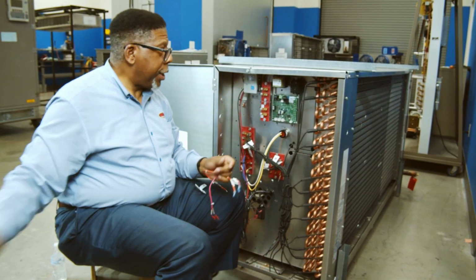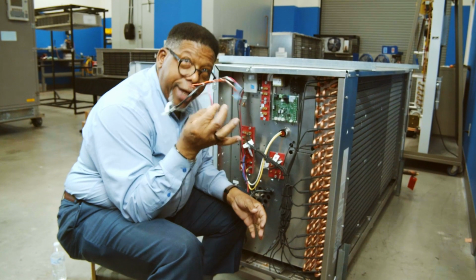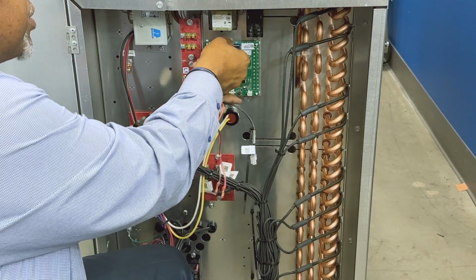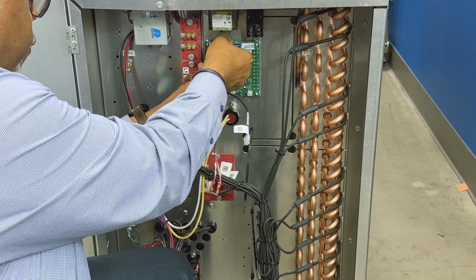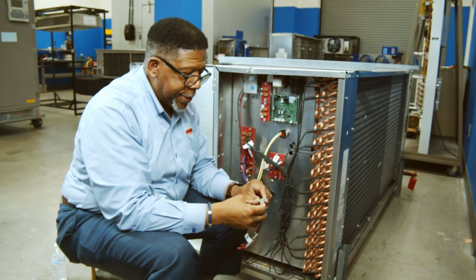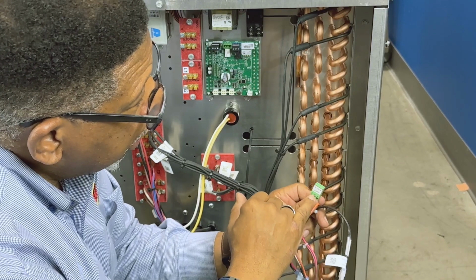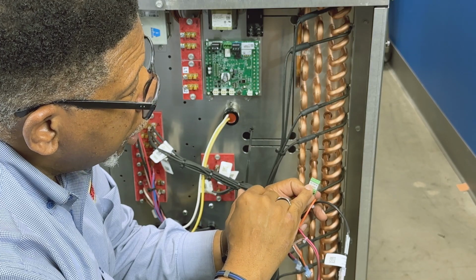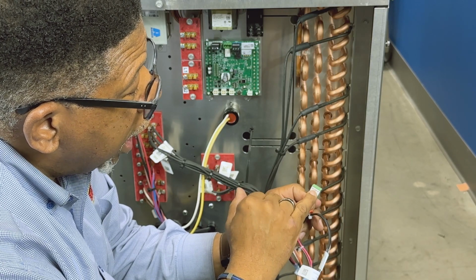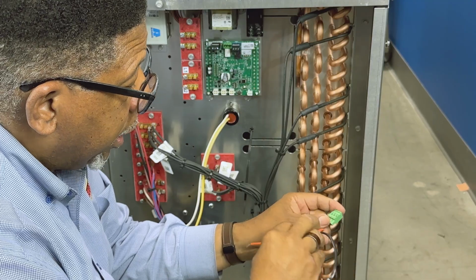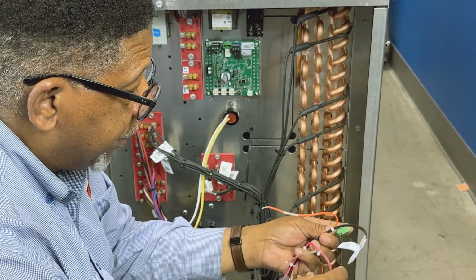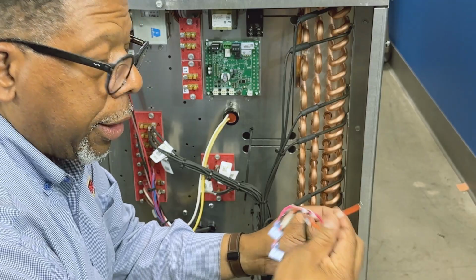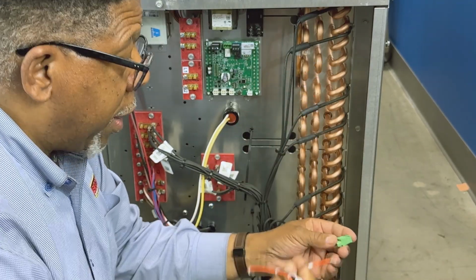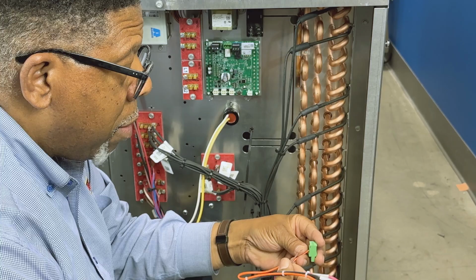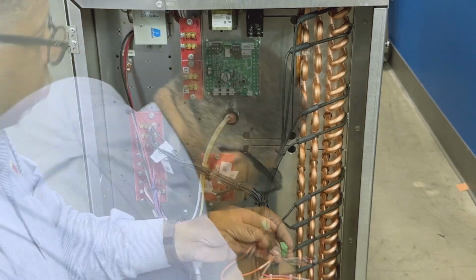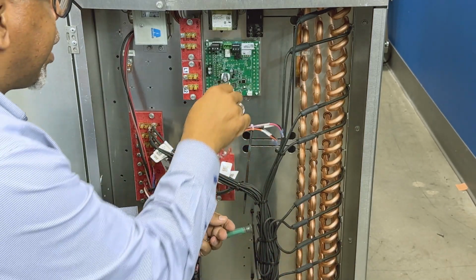Now we're going to go ahead and wire up our low voltage control wires in that harness there. We're going to pull the center tab out. This is the alarm tab for the actual RDS process. You see it has alarm, common, normally open, normally closed. We're going to use common and normally open, and that's wires number 5 and 7. That'll be an orange wire and a brown wire. Orange goes into common, brown goes into normally open. Plugging that back in. So let's plug that in now.